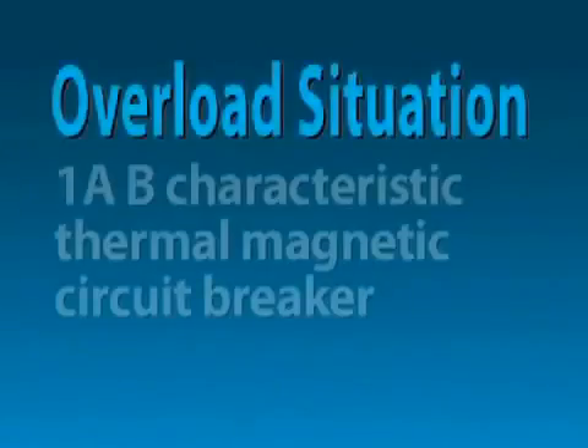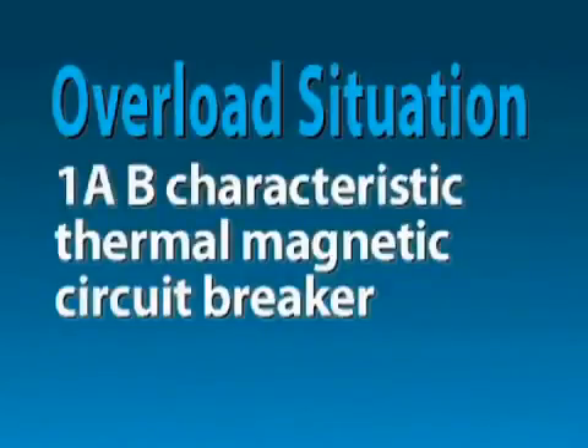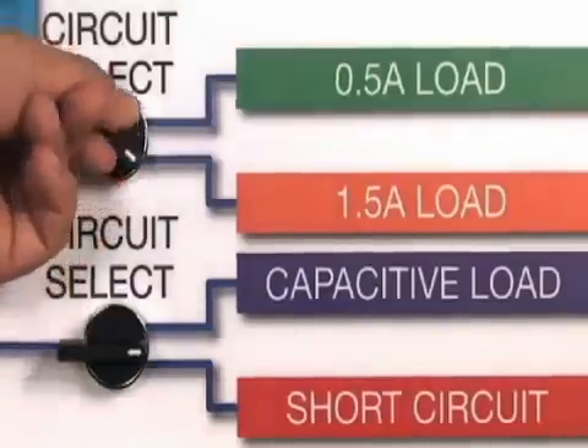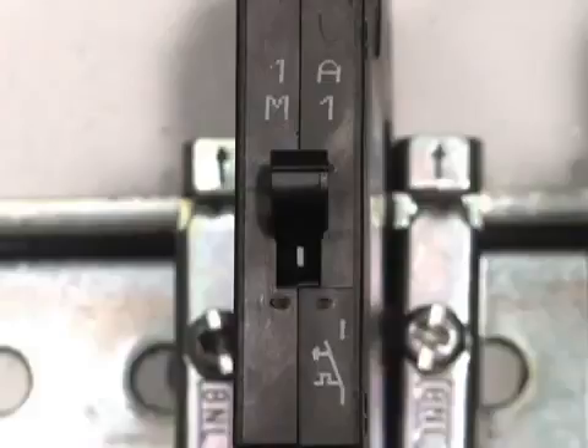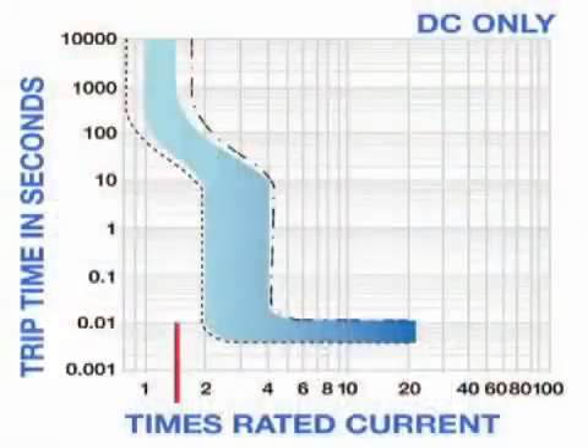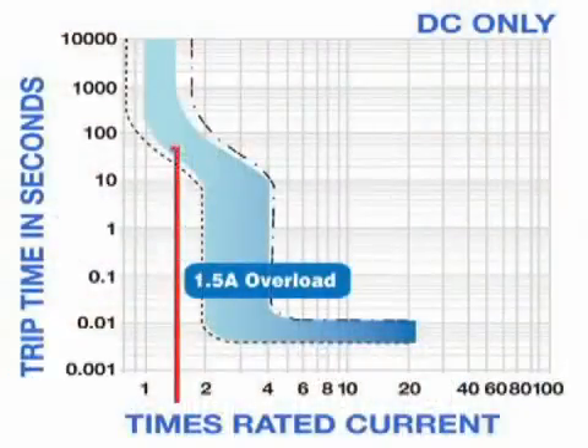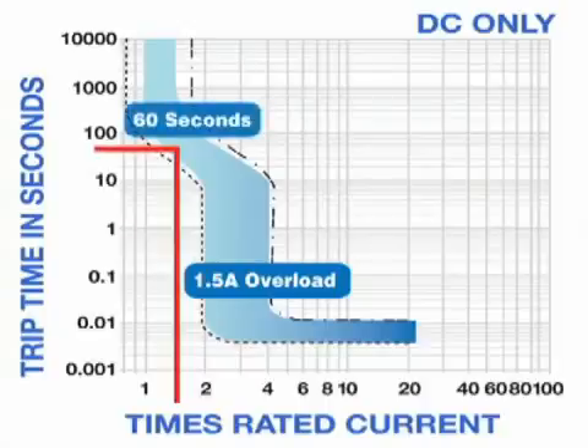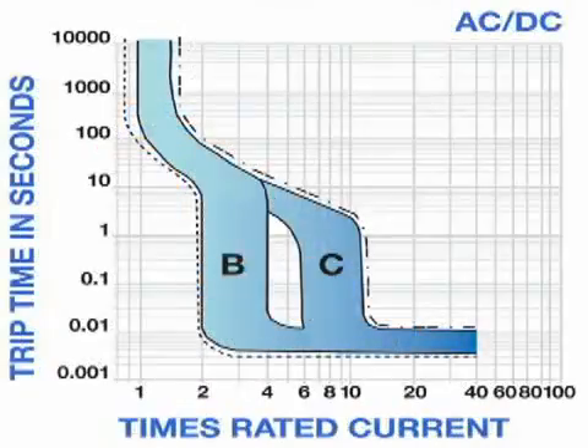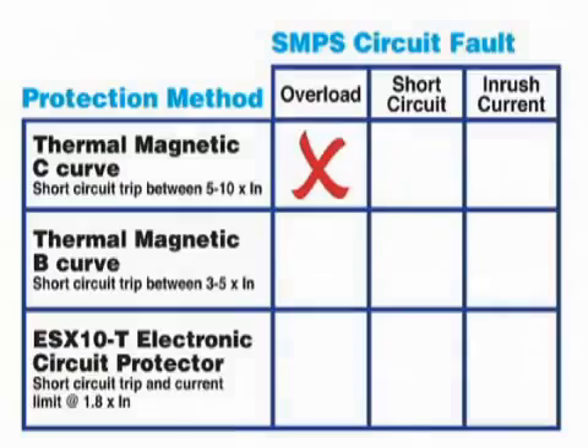Now let's see how a 1 amp B characteristic thermal magnetic circuit breaker will react to the same overload condition. Again, notice the breaker has not tripped and will not trip for approximately 1 minute. In both cases, with a C trip curve and B trip curve, the thermal portion of the breaker is the same. Only the magnetic trip portion is what changes, resulting in the same overload outcome. No overload indication for at least 1 minute.